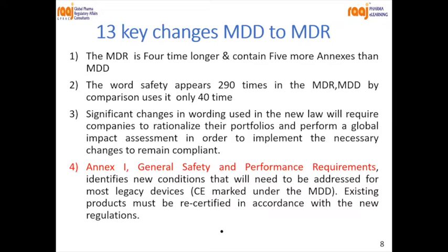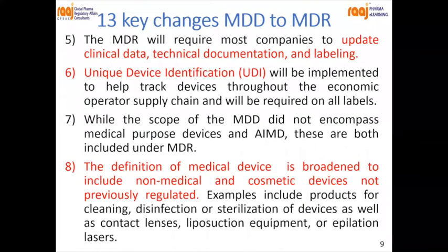As I said earlier, all the medical devices which are already in the market have to be recertified for the CE mark. The CE mark is used mainly in the EU market, and we discussed during the last lecture how the CE mark is done. Then the fifth change is that the MDR will require most companies to update clinical data, technical documentation, and labeling.